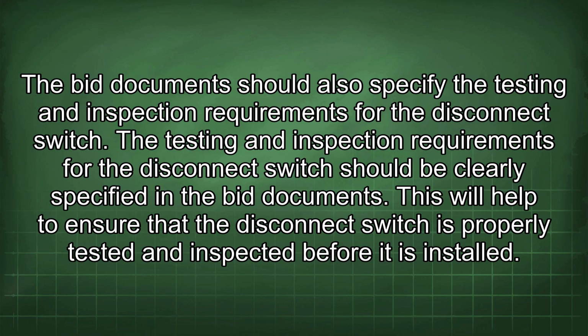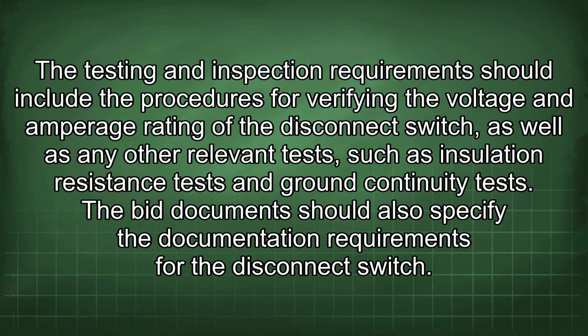The bid document should also specify the testing and inspection requirements for the disconnect switch. The testing and inspection requirements should be clearly specified in the bid documents. This will help to ensure that the disconnect switch is properly tested and inspected before it is installed. The testing and inspection requirements should include the procedures for verifying the voltage and amperage rating of the disconnect switch, as well as any other relevant tests such as insulation resistance tests and ground continuity tests.